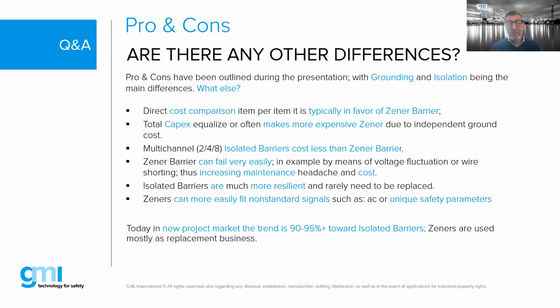If you have a special device, say for example a displacement sensor or something very unique that transmits a complex signal, the isolated barrier needs to take that signal and transfer it through a transformer. So it has to manipulate the signal and rebuild it on the other end, which means it needs to be specifically designed for that. There are some very rare applications out there where isolated barriers have not been designed yet, because the market is very limited or for whatever reason.